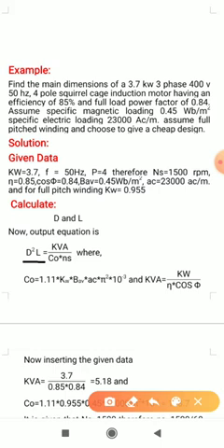So again, as we have already calculated in the previous example, in the same way we will calculate here first D square L by using the expression D square L is equals to kVA divided by CO into NS, and as you know that the value of the CO is 1.11 into kW into BAV into AC into pi square into 10 to the power minus 3, whereas kVA is equals to kW divided by efficiency into cos phi.